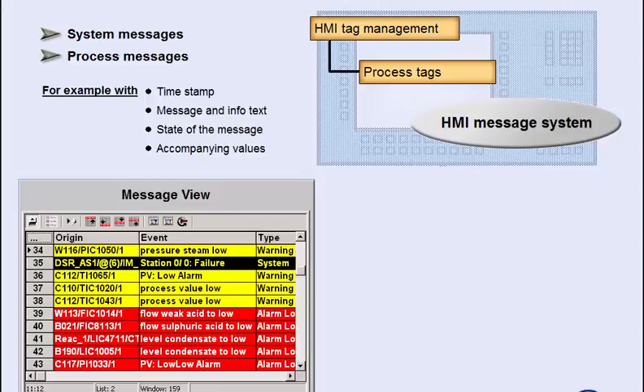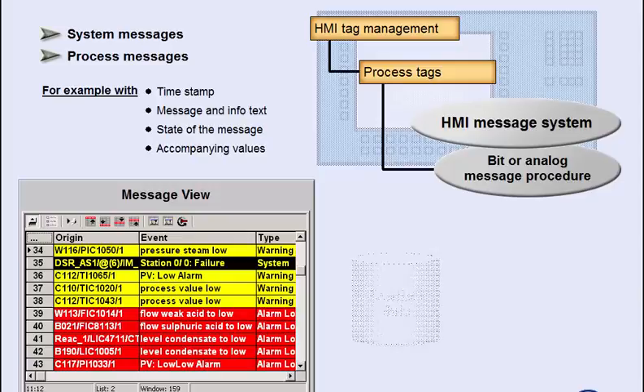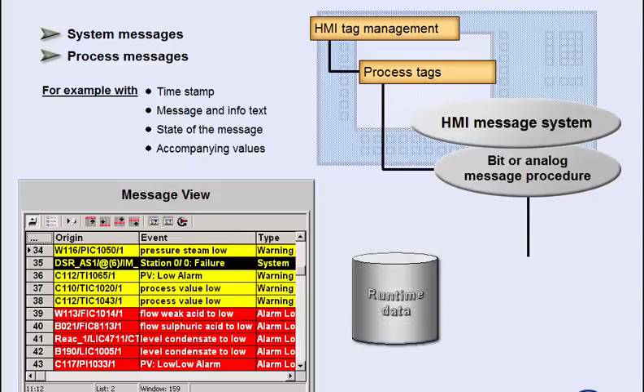One way to generate messages is the bit or analog message procedure, which is configured in the SIMATIC HMI software. If it detects that a binary tag has changed status, or that an analog tag has exceeded a limit value, the HMI system triggers a message and has it output with a timestamp generated for it. With this procedure, the HMI system handles both the detection of events and the management of messages.